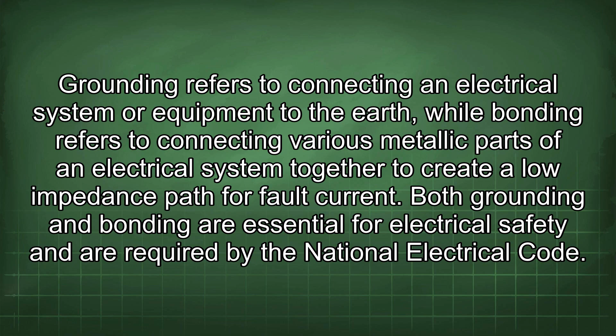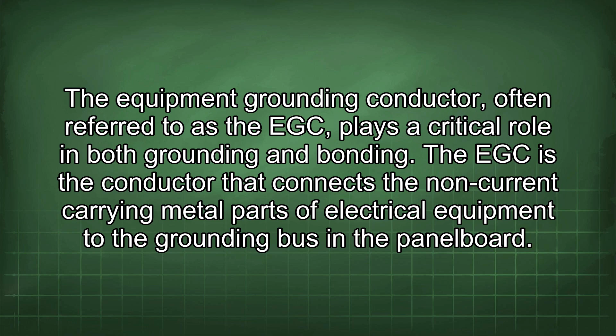Both grounding and bonding are essential for electrical safety and are required by the National Electrical Code. The equipment grounding conductor, often referred to as the EGC, plays a critical role in both grounding and bonding. The EGC is the conductor that connects the non-current carrying metal parts of electrical equipment to the grounding bus in the panel board. This conductor provides a low impedance path for fault current to return to the source, allowing overcurrent protection devices to quickly trip and clear the fault.